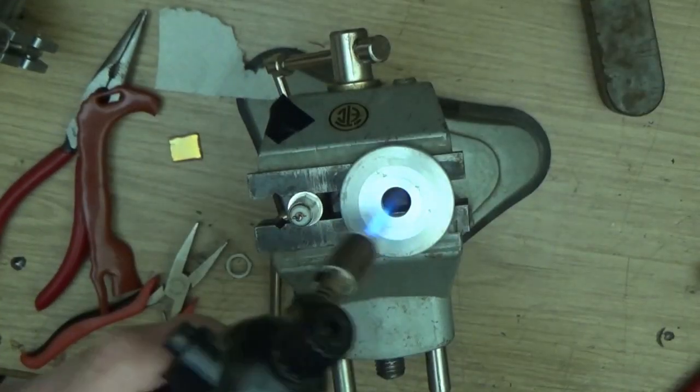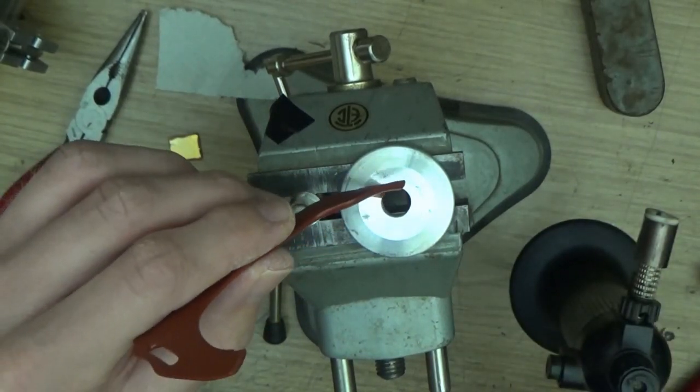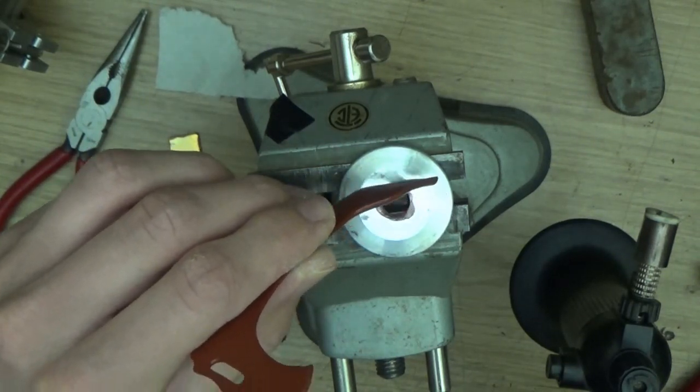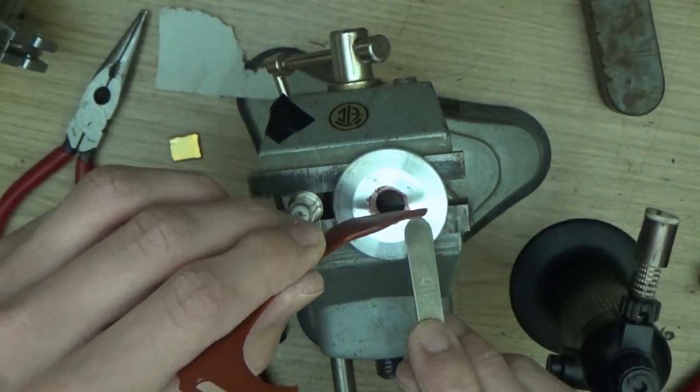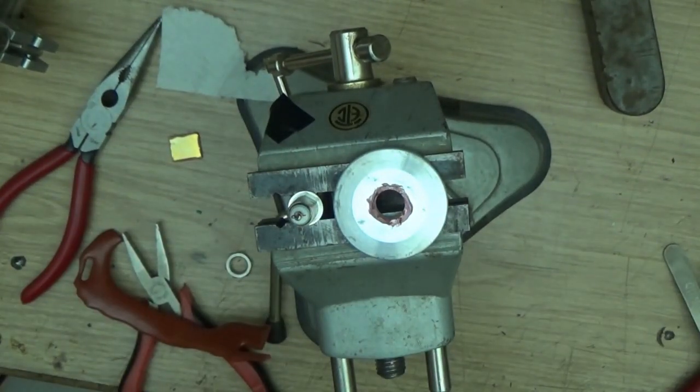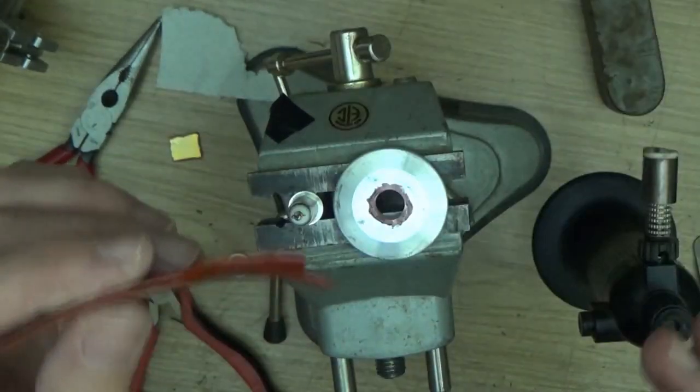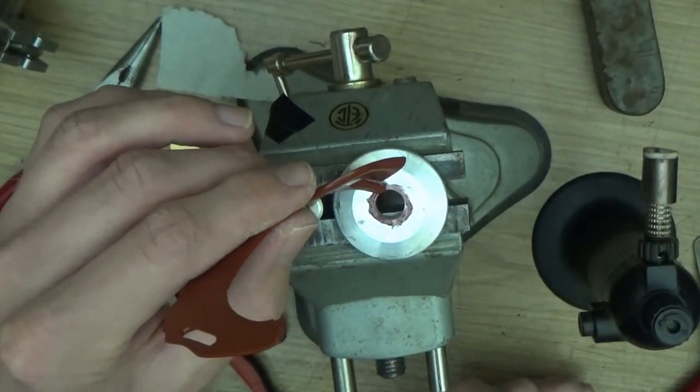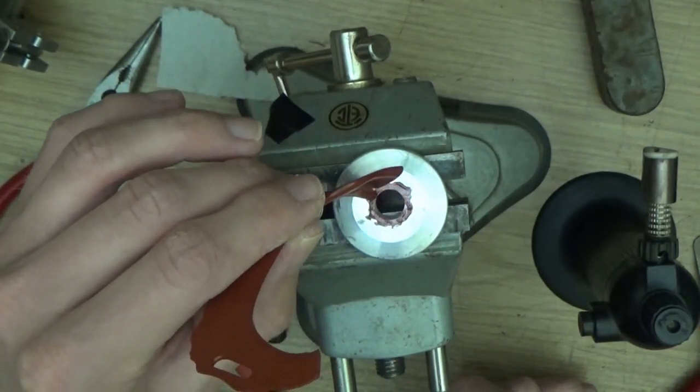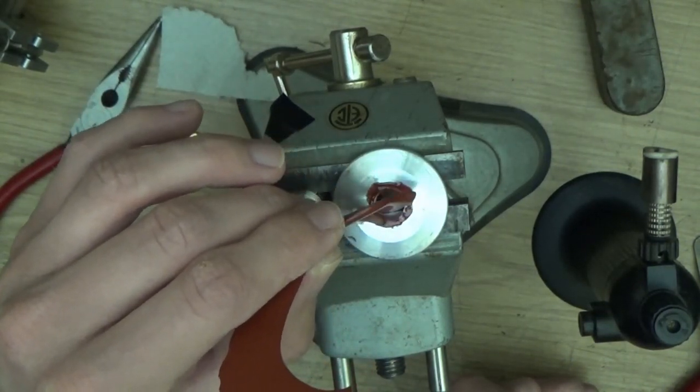We preheat. I have no idea how hot that got, but we'll find out. Take care not to overheat. You don't want to burn the grease because then it'll contain soot, which is detrimental to the sealing. And you might need to reheat occasionally to make it flow evenly.